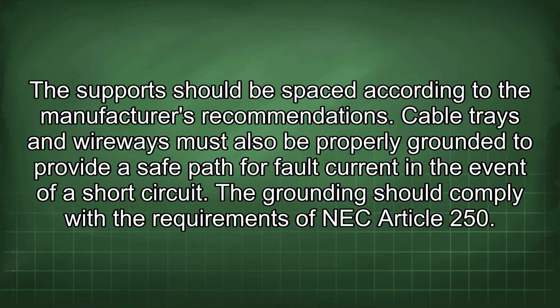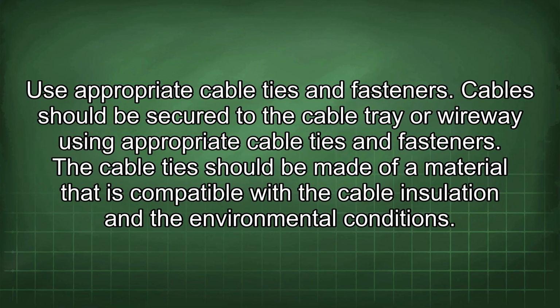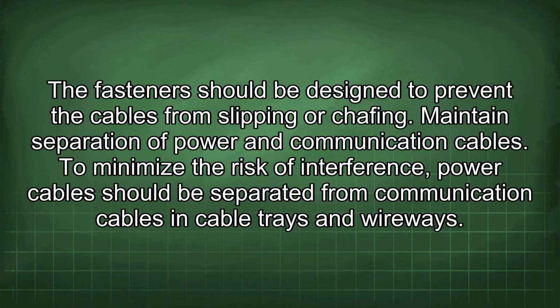Cable trays and wireways must also be properly grounded to provide a safe path for fault current in the event of a short circuit. The grounding should comply with the requirements of NEC Article 250. Use appropriate cable ties and fasteners. Cables should be secured to the cable tray or wireway using appropriate cable ties and fasteners. The cable ties should be made of a material that is compatible with the cable insulation and the environmental conditions. The fasteners should be designed to prevent the cables from slipping or chafing.